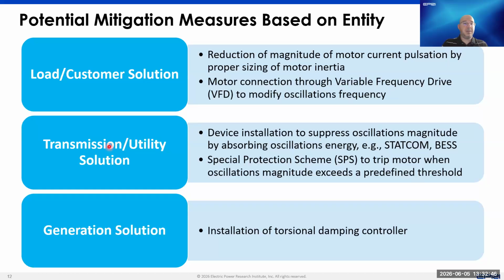The other category is the transmission and utility solution, so what the transmission utility, Entergy in this case, could do. Two options we listed are to install devices to suppress the oscillations, such as STATCOMs or batteries. Now there's a lot of discussion about e-STATCOMs and GFM batteries, etc. Or another option could be to design and deploy a special protection scheme to trip the motor if the oscillation magnitude is significant and exceeds a predefined threshold.